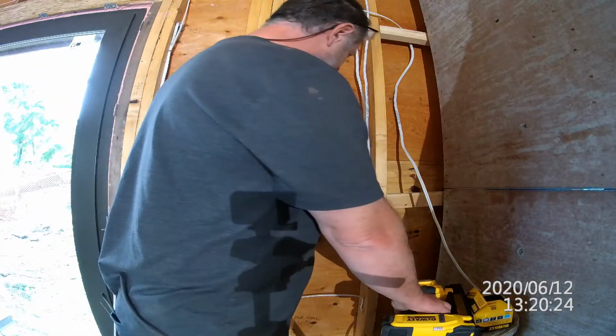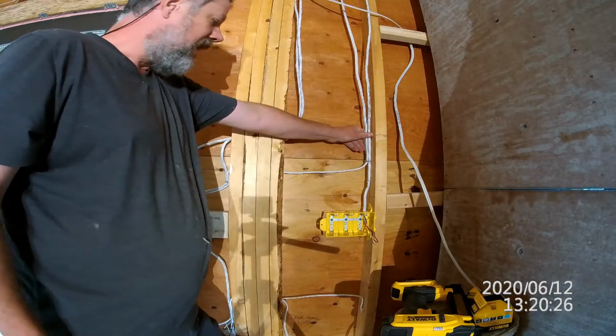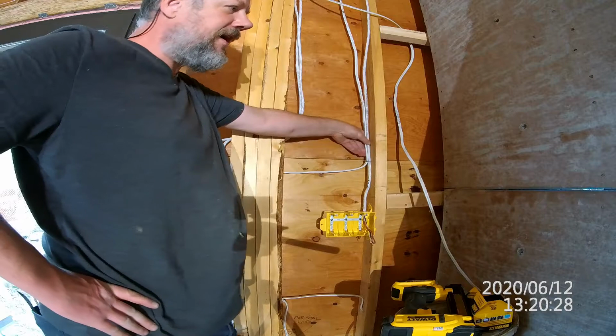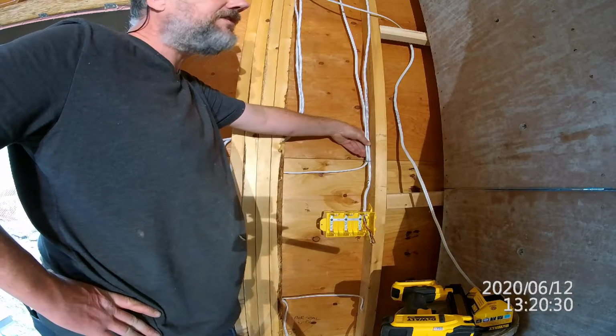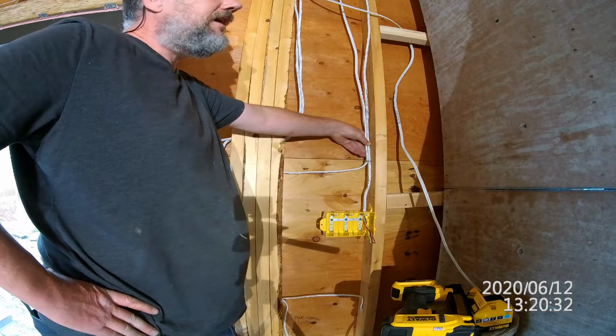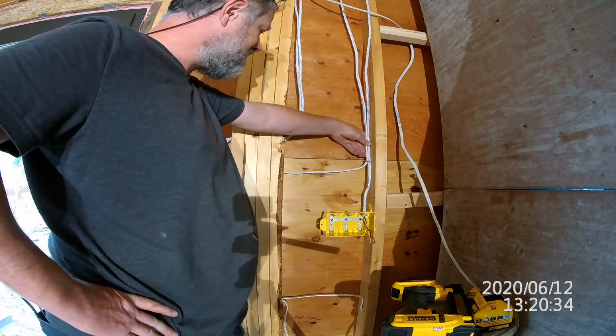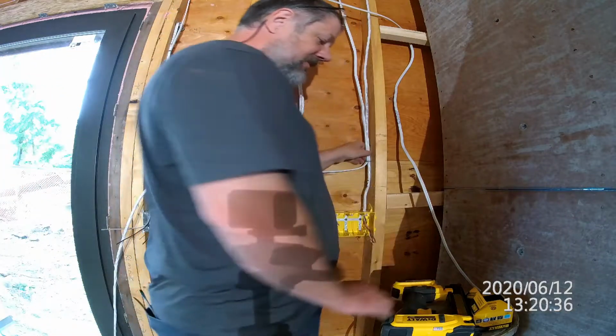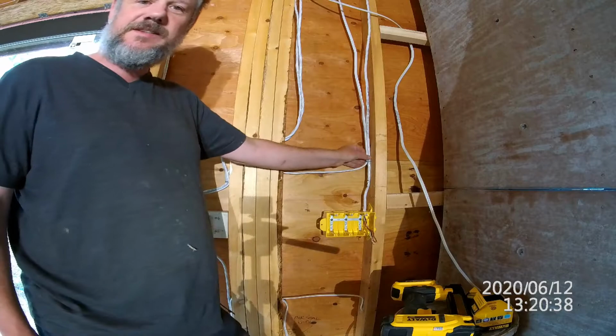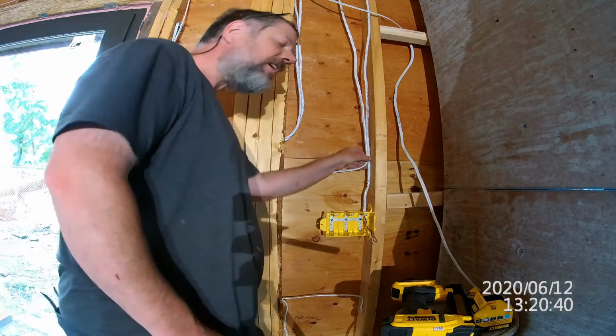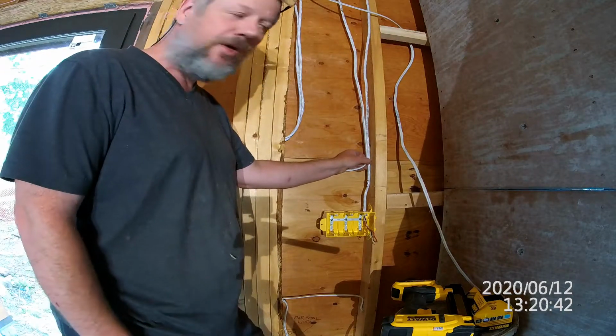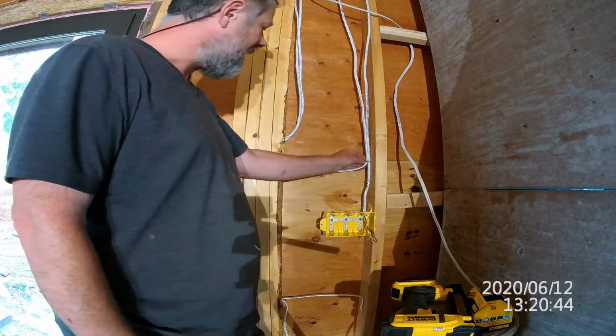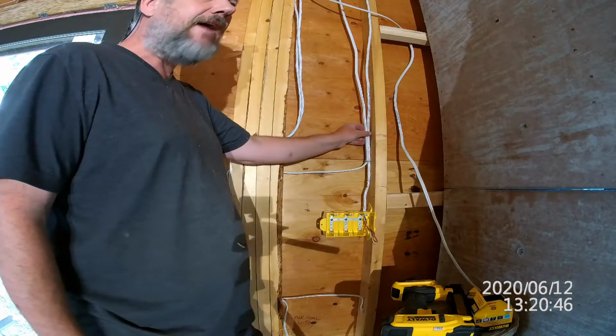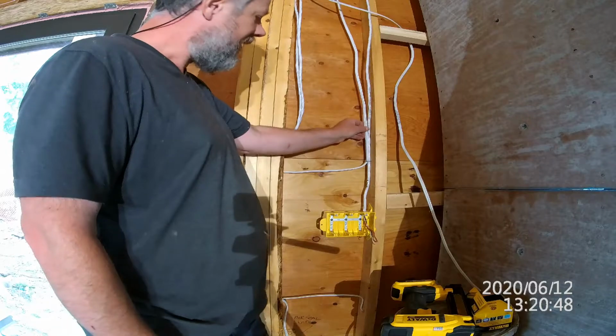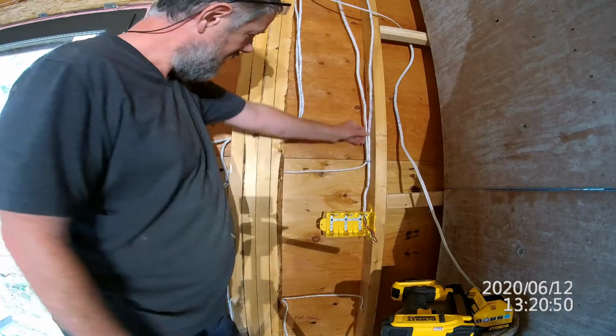Now let's talk about movement. A lot of forums where I looked at various electrician comments, they did not like this because it doesn't tightly staple the cable. But it's not supposed to tightly staple the cable. It's actually against code to have a staple so tight that the cable does not move as it's doing here.